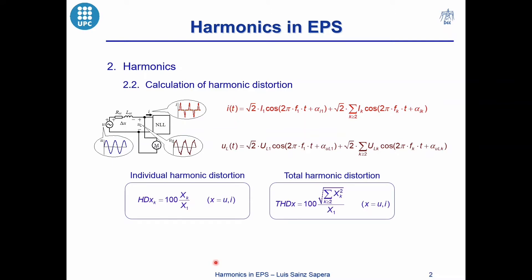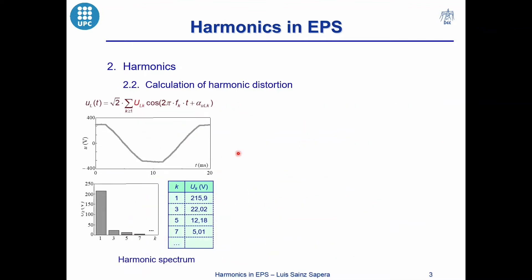Determining the distortion of the currents is useful to know the quality of a nonlinear device — that is, if the distortions are greater than 10%, the device is a very pollutant load. Determining the distortion of the voltages is useful to know the quality of the voltage at the point of common coupling or in the plugs — that is, if the distortions of the voltage are greater than 5%, the voltage waveform we receive is very polluted.